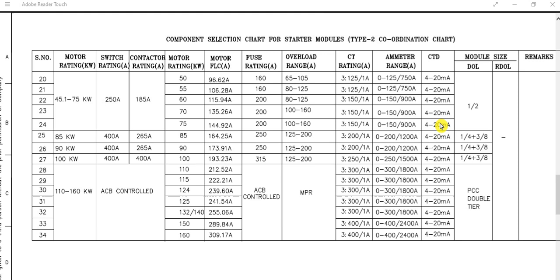And the last column is CTD, that means current transducer. The current measurement is already measured by the current transformer and shown on the ammeter. The CT is connected with the ammeter, so in the ammeter you can see the reading. But if you want to see this current measurement from DCS or from PLC or any other remote panel, then you need to transmit this signal as a 4 to 20 milliampere DC signal. So this is the purpose of this current transducer.